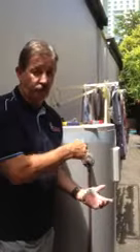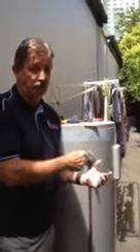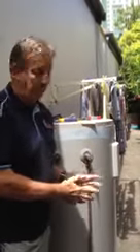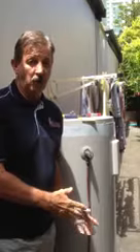All you do is: number one, grip the valve; number two, lift the valve, allowing the water to spray out; number three, allow it to go back. Simple as that. You only have to lift the valve for two seconds — that's all that's required. It's just literally to wash the valve out and wash out the overflow line to make sure it's clear.